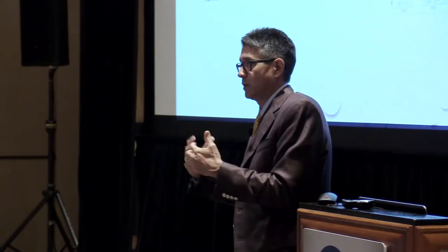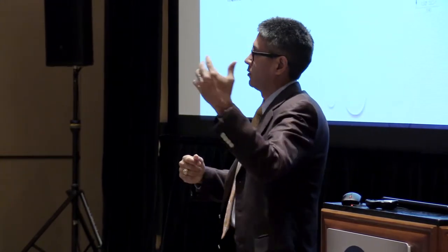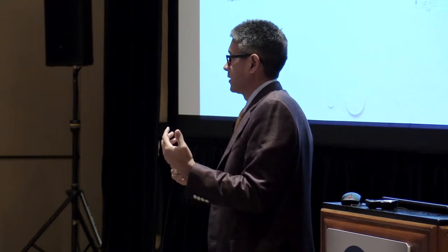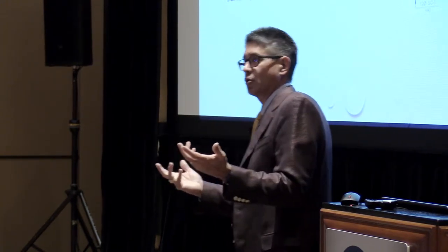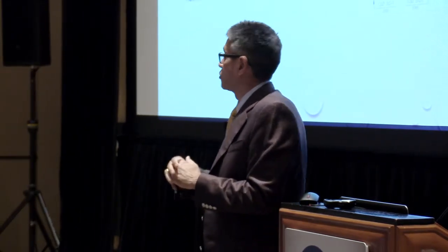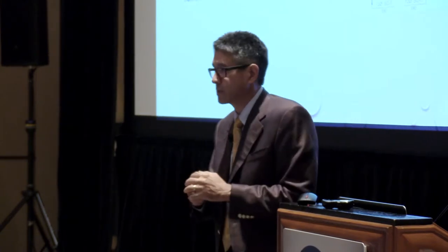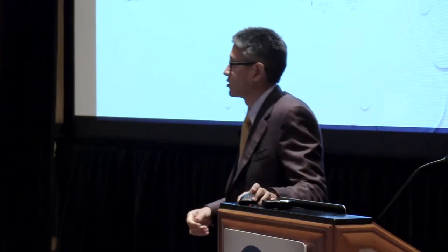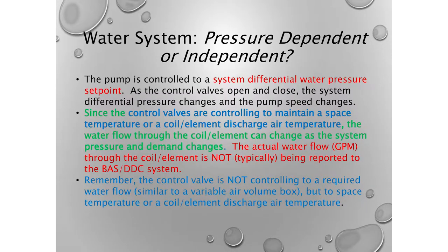Your load's changing, but your one box is not changing. And then keeping in mind, what's that VAV controlling to? And that becomes the other thought process. It's controlling to an airflow set point, and it's also reporting an airflow set point back to the system. So that's where you can start to understand that you have pressure dependent versus pressure independent.